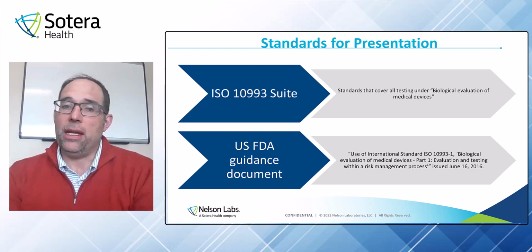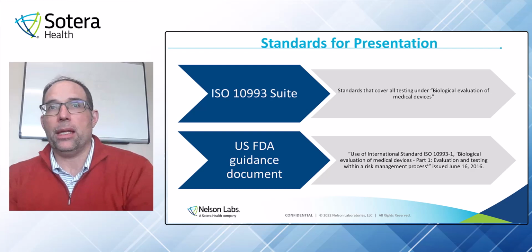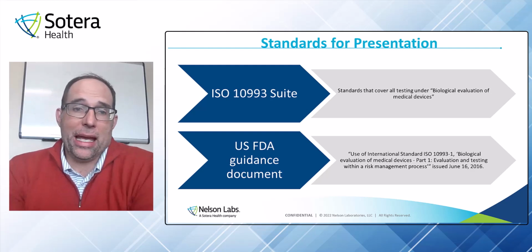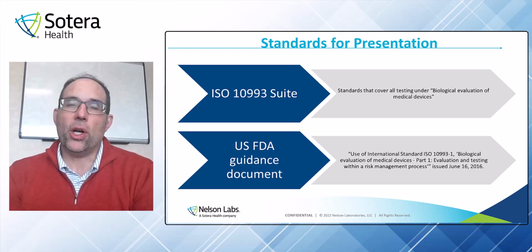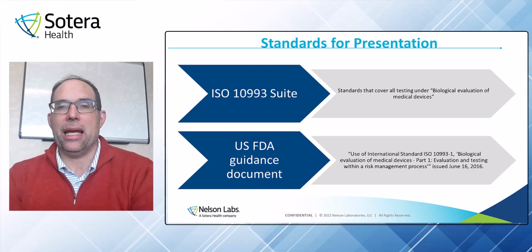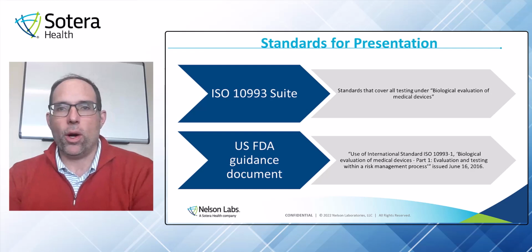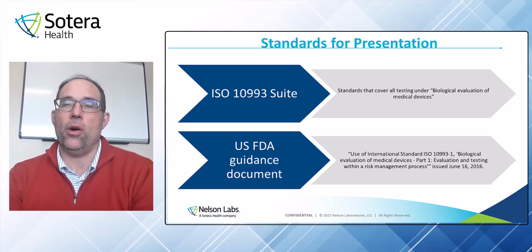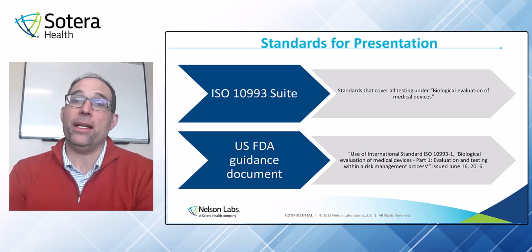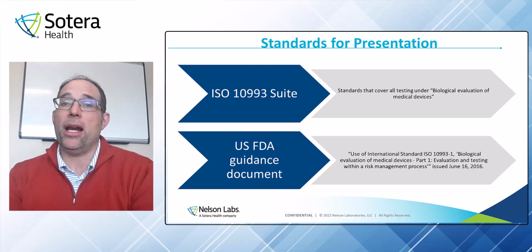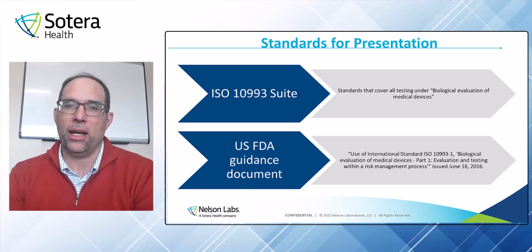But then we also have the FDA's guidance document. So in Europe, the ISO standards are kind of like a law. As a notified body, they'll look at that standard and interpret it, but they'll basically follow it as they evaluate the device for a CE mark, kind of word for word. So if the standard in Europe for the -23 says you should consider in vitro irritation first, your notified body is going to want you to consider in vitro irritation first before you jump to an animal.